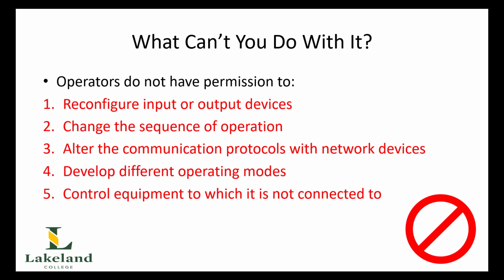Well, as operators, we're not able to reconfigure those, meaning they are set up the way the instrument tech sets them up. We are not qualified, nor are we competent to go making changes like that. So we are locked out of doing things like that. On a similar note, we are also not able to change sequences of operation. For example, we couldn't adjust it so that the pre-purge is done after we light the boiler off. Well, that would be ridiculous, wouldn't it? You can't adjust any sort of sequence like that. Again, we are not competent or qualified to do so.